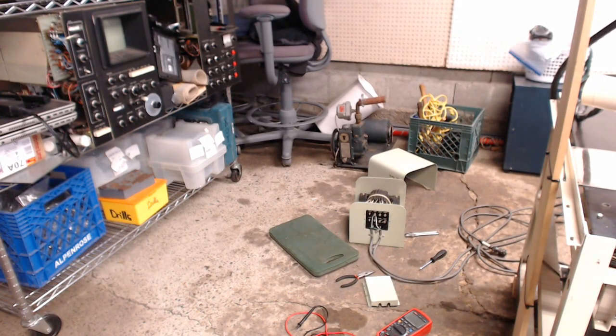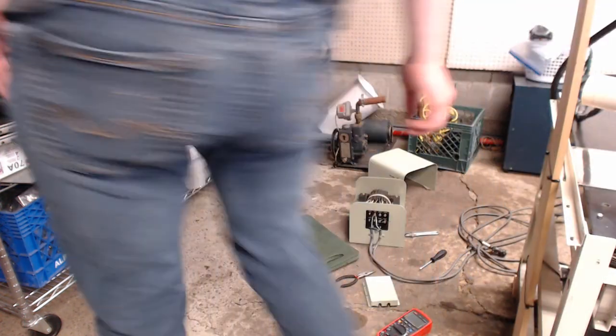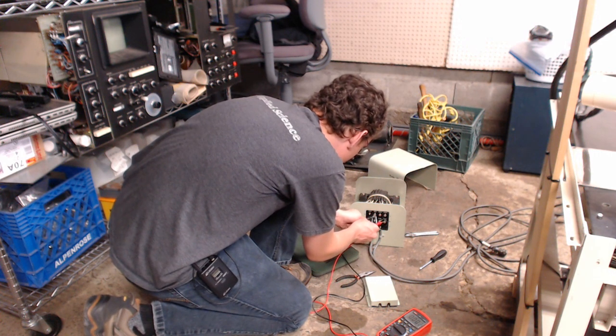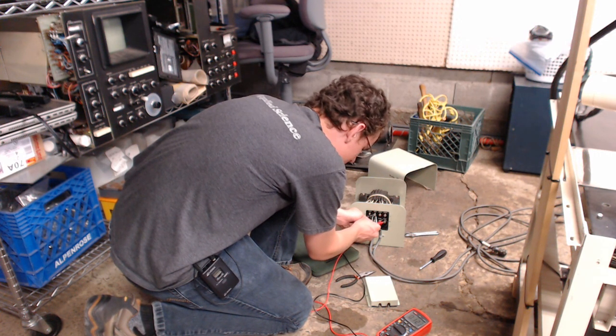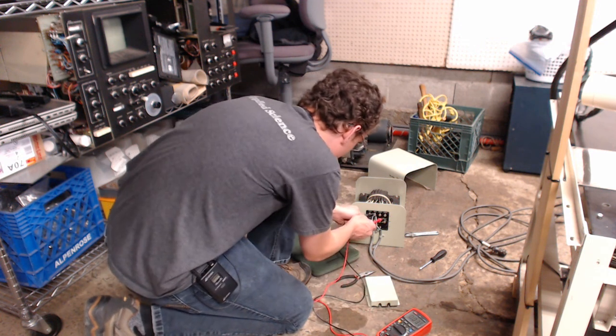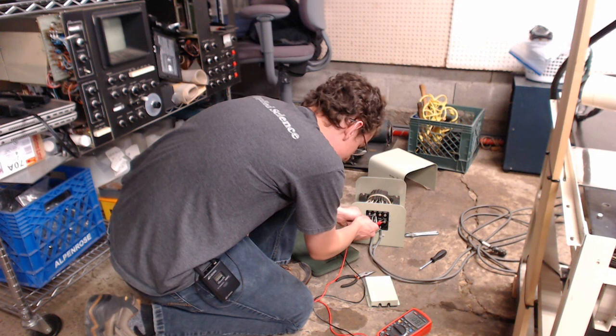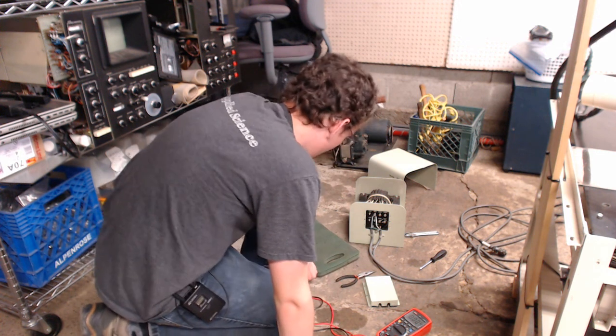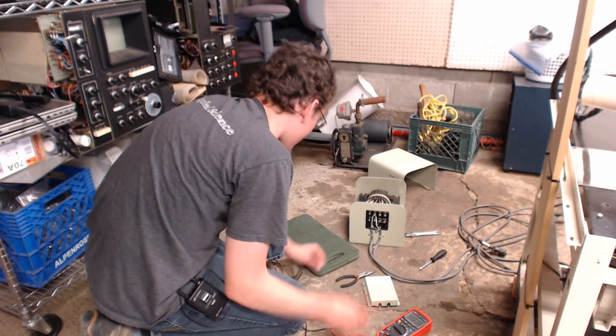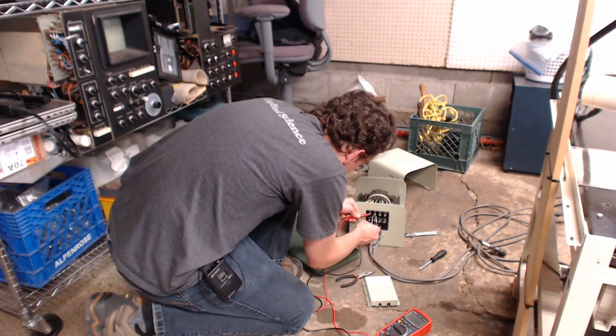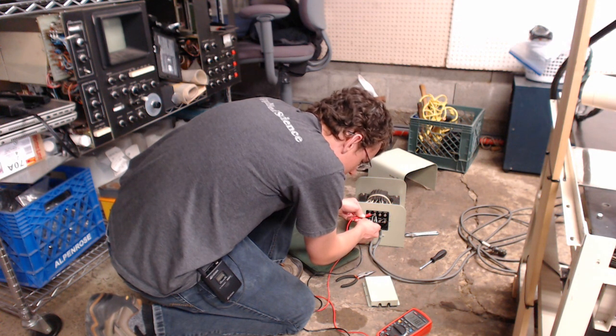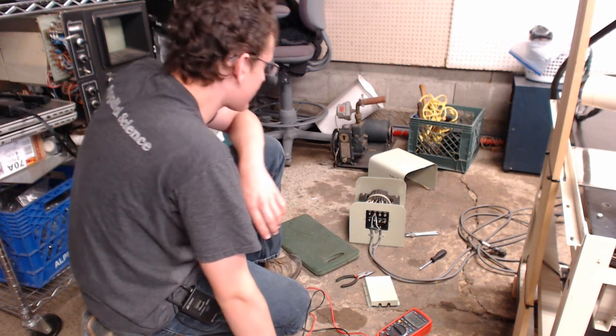Get everything plugged in. No nasty noises. Get it out of DC. 109.5, that's way too high. Okay. What's my line current at now? My line voltage must be higher now. Wow, line voltage has gone up by a half volt.